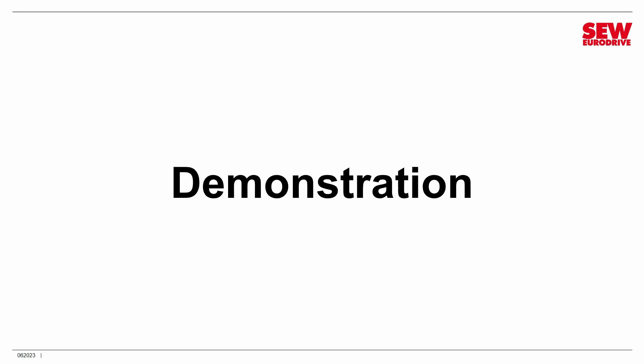We're ready to do some work with our Movimot. I'm in Movitools Motion Studio, connected to my Movimot by a USM21A USB adapter. I've scanned into my network and the Movimot is detected — you can see it in the lower left under Network. I have the parameter tree up here. The first thing we need to do is factory reset our Movimot and then change it from Easy Mode to Expert Mode. Factory resetting returns parameters to default values, so I'll open main group 8, subgroup 0.